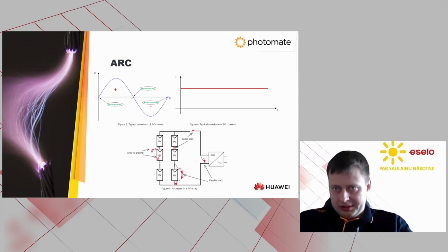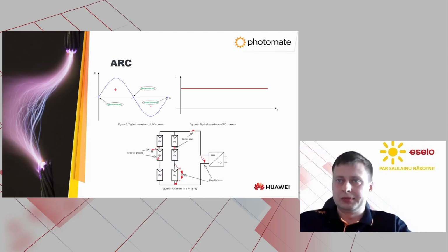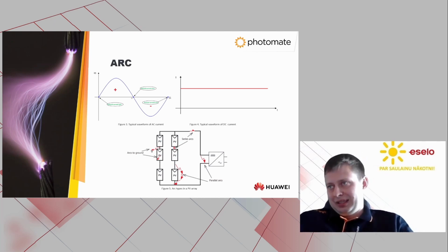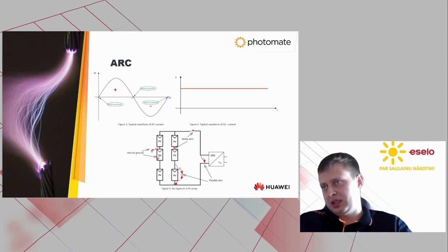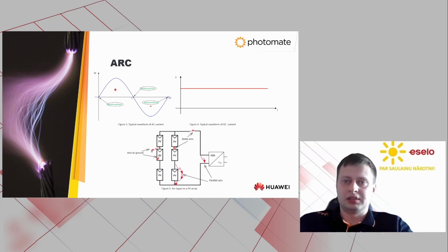In AC circuits, current is changing direction 50 times per second. And this means 50 times per second, the value of the current is 0. In DC, it is opposite. The current is always at the same level and always in the same direction. So if an arc in AC appears, it can extinguish automatically when the current is crossing 0. But with the PV installation, it is not extinguishing automatically.